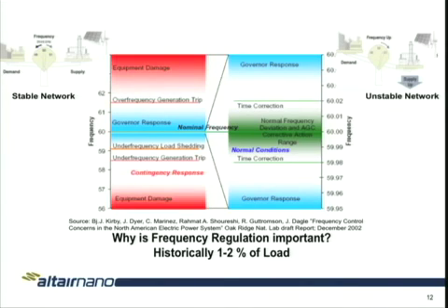And as it's telling it, hey, we need another 20 megawatts, or we need another 10 megawatts, the generators will start ramping up. And what you see in that time period is not a generator that suddenly says, okay, here's another 20 megawatts, or let me take off 20 megawatts. They start ramping. And they have 10 minutes to get to that. That's part of the tariff. You have 10 minutes to get to that point. And of course, we're saying a signal every 4 seconds. So as they're ramping up, another signal is coming in, maybe to ramp up higher, or it could be to ramp down. And you're constantly trailing the signal. And that's where limited energy storage resources bring value right now.